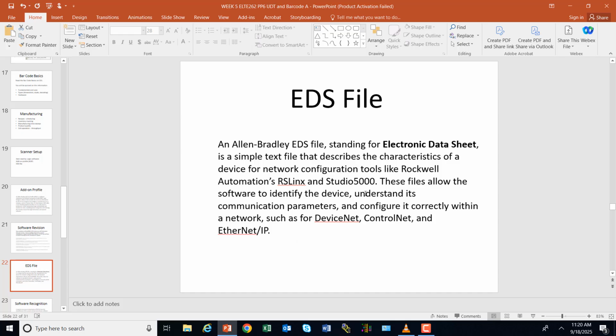And so if you get these add-on profiles and these EDS files all set up, the beauty is when you go to RSLinx and you go RSWho, if you have a barcode scanner on RSLinx, boom, a picture of the barcode scanner pops up, just like when we do a PowerFlex drive, a picture of a VFD pops up, or a picture of a robot would pop up, if you had all this stuff configured as it should be. If not, you can still use it, you're just going to have a question mark that says, hey, there's something plugged into me.